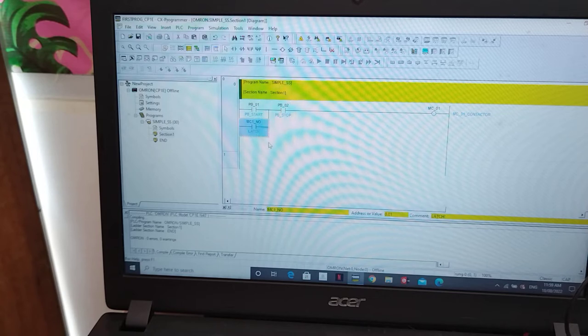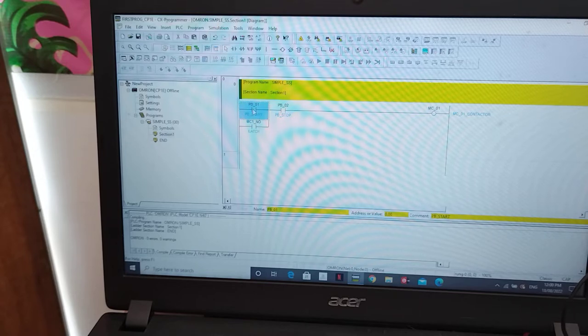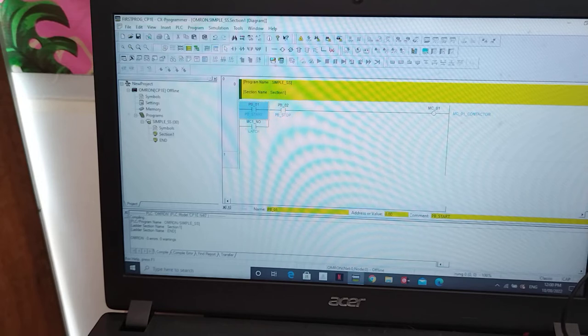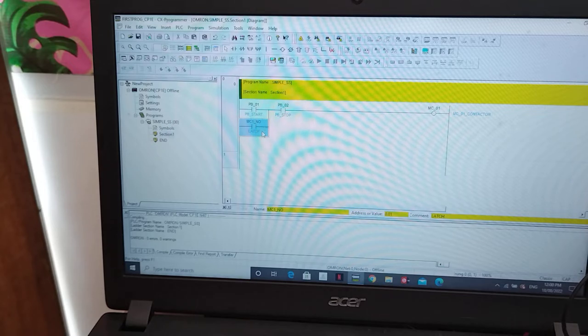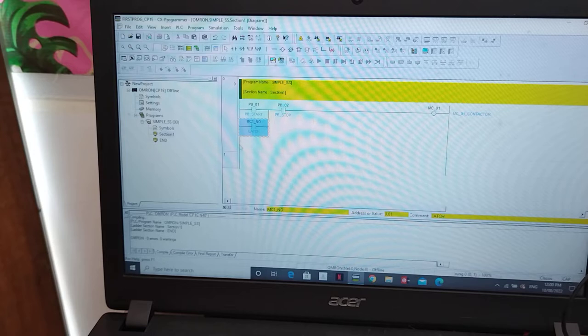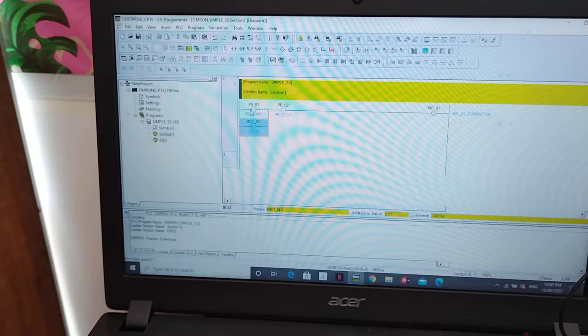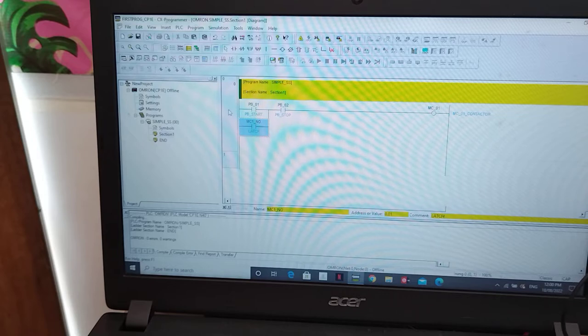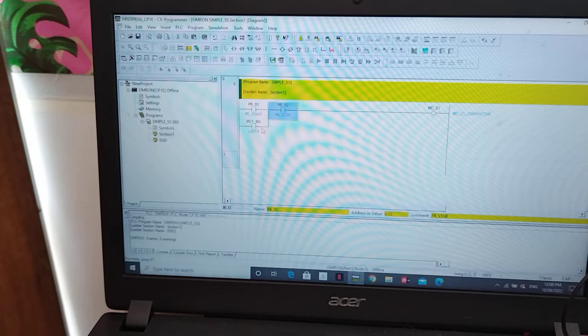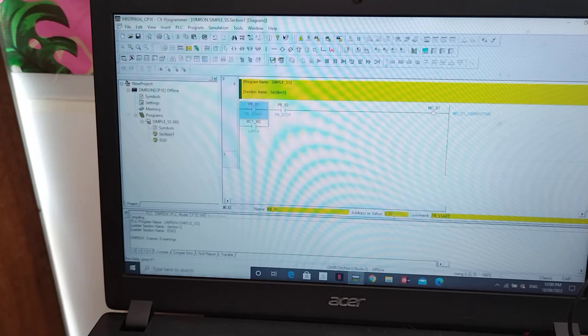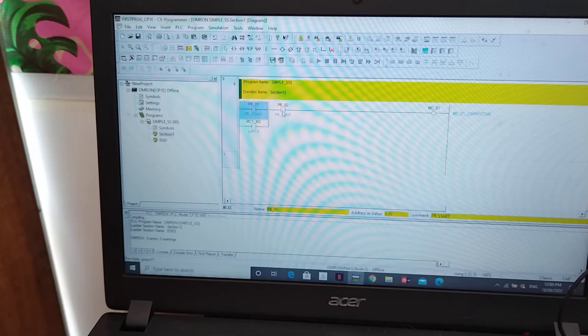Down here is my latching. In motor control, this is the latching contact. Because as we know, push-button is momentary — PB01 is momentary. It will try to energize the coil, but we need a latching contact that will keep it energized. So I have my next symbol, MC_NO, which is the normally open contact from the magnetic contactor of my motor. I'm using this as a latching contact, so that when I push the push-button switch and then release it, my coil will stay connected from the left rail. Once you have written your ladder program, you need to keep checking the addresses — there should be no redundant addresses.